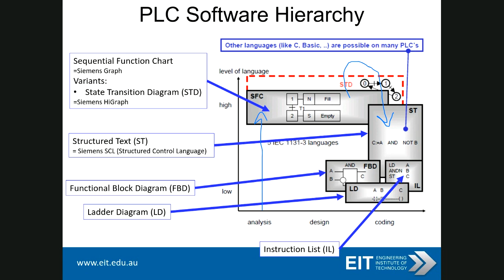You can actually draw your process in SFC and then continue to program the functionality in the various steps in something like structured text, which is a high level language, or in one of the lower level languages such as function block diagram, or instruction list, which is low level, or in ladder logic. My personal favorite is to analyze in SFC and then code in structured text. This solution is then rather portable because structured text is highly portable, and the analysis is eased by doing it in SFC.